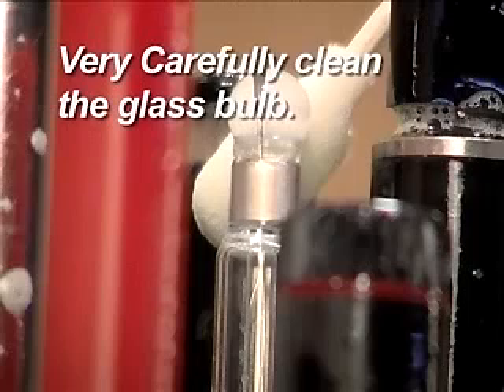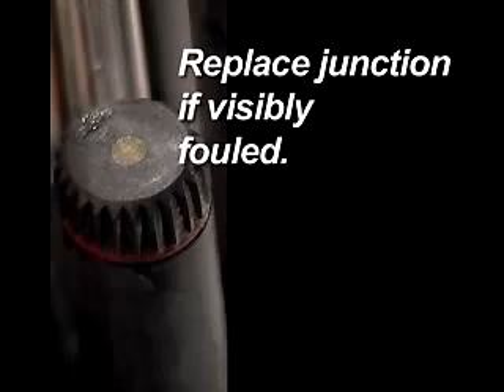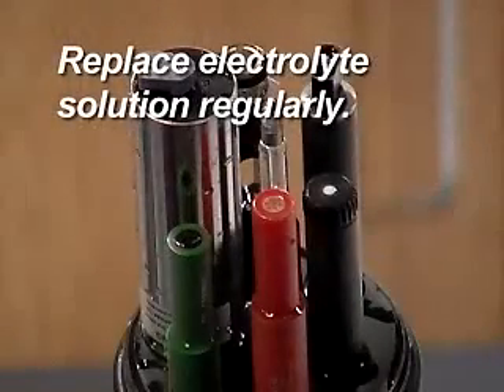Very carefully, clean the glass bulb with a very soft brush and mild soap. The bulb is made from extremely thin glass and is very fragile. Replace the reference junction if it is visibly fouled. Water with strong biological activity tends to foul the junction more rapidly. Replace the electrolyte solution regularly. Water with very low levels of dissolved solids or high flow rates will leach the salts out of the solution and dilute it more quickly. Your specific water conditions will determine how frequently this should be done.